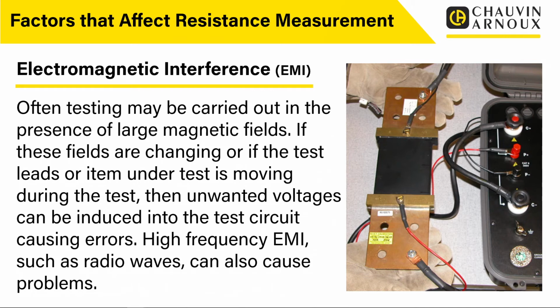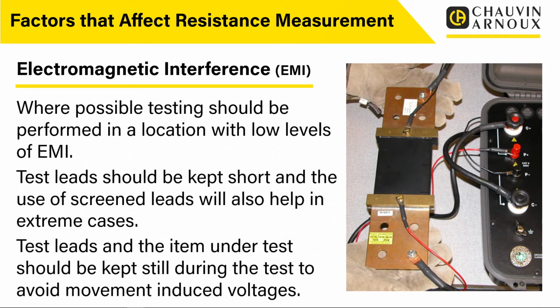Luckily, most test equipment is quite well screened and shielded against these things, but they can still cause issues. So where possible, testing should be performed in a location with low levels of electromagnetic interference. That's something to think about when we're carrying out the testing. Do we need to do it right by the side of the mains transformer, or could we do this at another location where it's not going to be as critical?